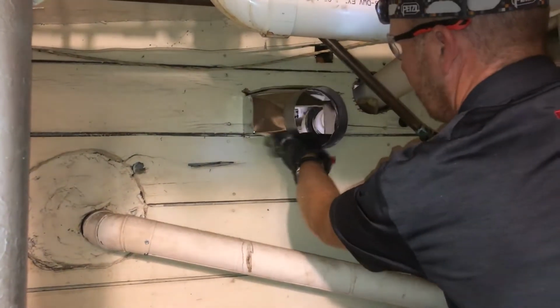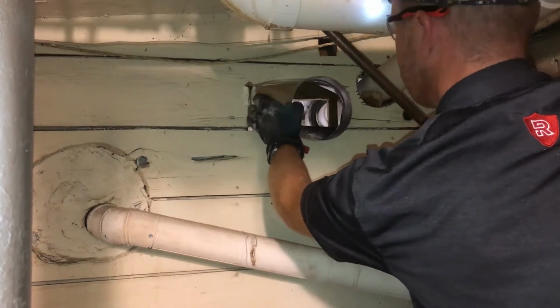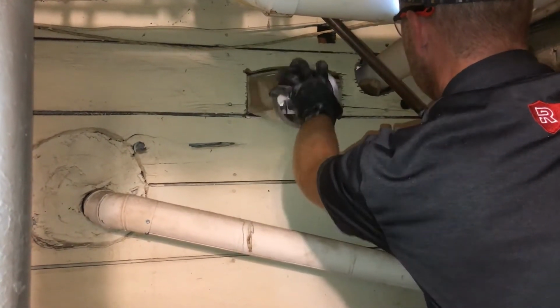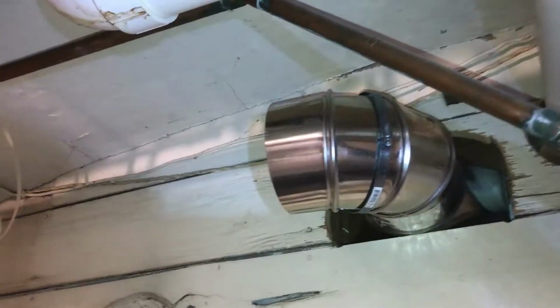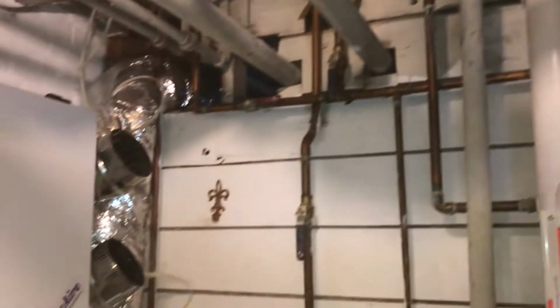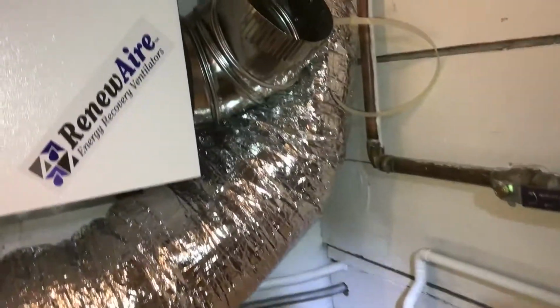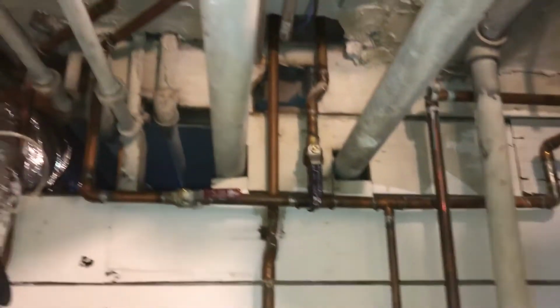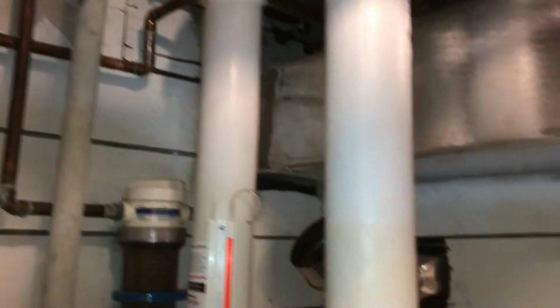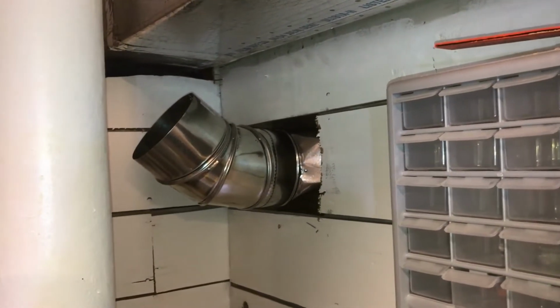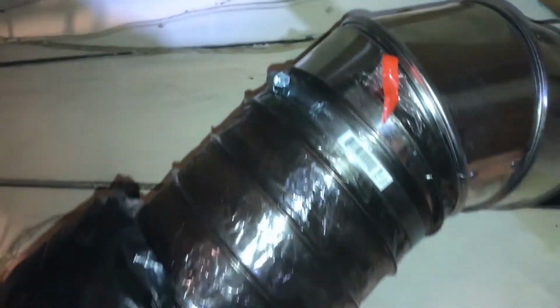So as you can see, we're going to have our ductwork run right through that wall and then connect a vent grill on there to blow the air through. And we're going to run our flexible ductwork up through the wall right there. As you can see, we already have another vent installed there. That's going to be where we're drawing our room air, and that room air is going to flow then through the ERV unit too. So that's how this works. We've got fresh air blowing in, the room air blowing out from inside the house, and then we have our fresh air coming in and our exhaust going out. So really those 4 flexible duct runs we're installing.